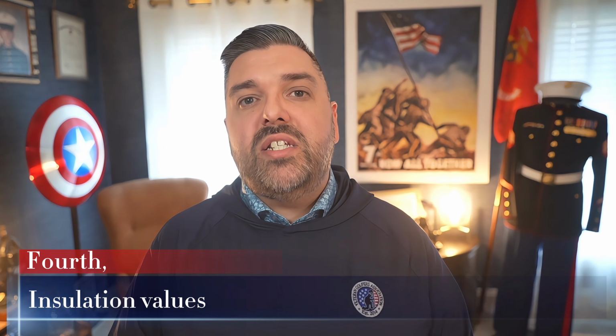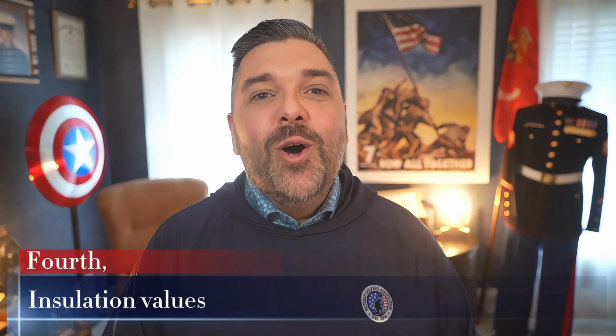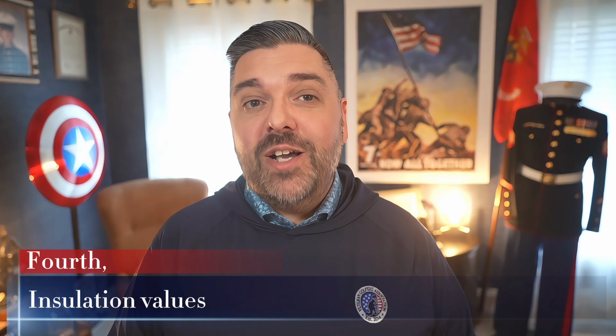Use them. All right, let's move on to insulation values because this is where I see some truly creative inputs. When a contractor enters insulation values into Manual J software, they're supposed to enter what's actually in the building or what's going to be there after weatherization. The actual R value of the insulation in the actual walls and ceiling. What often gets entered instead is what the contractor thinks is probably there based on the age of the house and what typically is installed at that time.